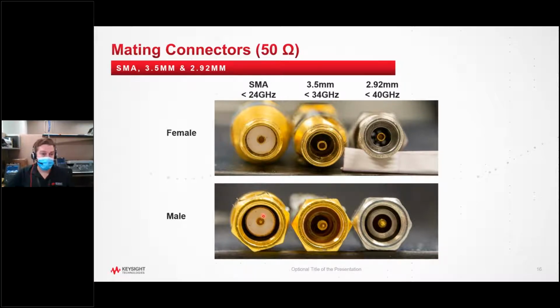Old timers will tell you never to mate an SMA with a 3.5. The reason is SMA connectors used to not be precisely controlled by specification, so the pin depth and pin diameter were variable. You could take that male pin, plug it into a 3.5 female, and destroy the receiving section by expanding it past the point of return. Nowadays that's much less of a problem—as long as it's not a 40-year-old SMA connector, and you inspect it, it will mate safely with a 3.5 and even a 2.92 connector.